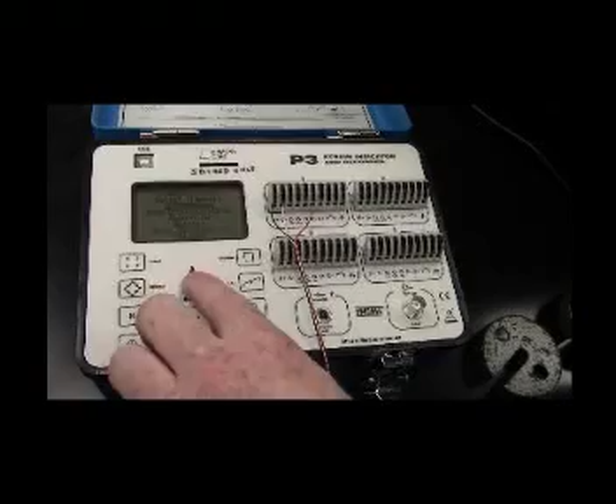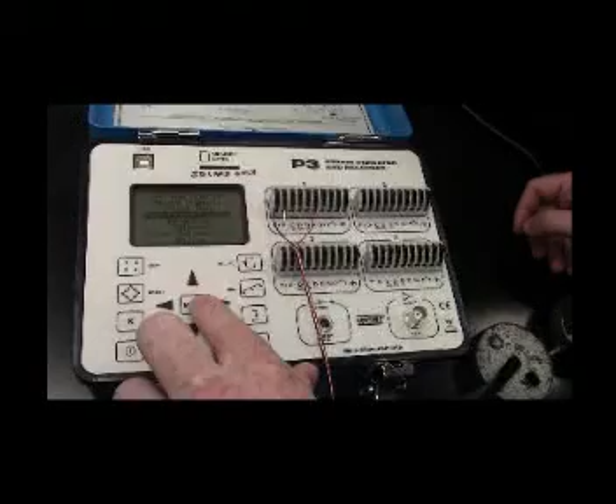So first we need to make sure everything's set up correctly. We're going to go into the menu on the strain recorder, and the first thing we're going to do is select the bridge type. In order for this to function properly, we need to have a half bridge set up. The second thing we need to do is to make sure we're in units of pounds. So under gauge factor/scaling, we can make sure that channel 1 is set up in units of pounds.